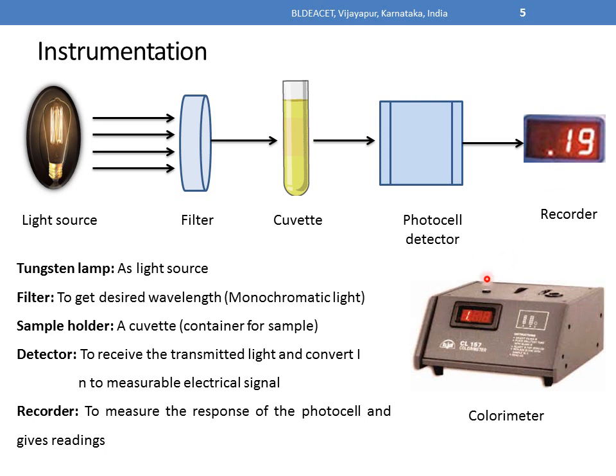This is how a typical colorimeter looks like. You can see a small hole which is the sample holder — in that sample holder the cuvette containing the solution is placed. From the light source, light is passed through the filter and made to fall on the solution. The transmitted light is detected by a photocell detector, which converts it into an electrical signal, and that signal is displayed by the recorder as an absorbance or optical density value.